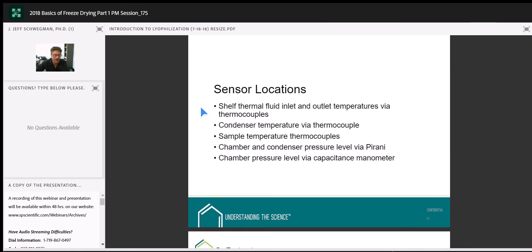First question: You mentioned the sublimation front is curved — is this applicable for both primary and secondary drying? What are the differences? There's no sublimation front in secondary drying. When primary drying is done, all the sublimation of ice is complete — we see the sublimation front come down as essentially a sphere at the end of primary drying. In secondary drying, all that's gone and we're just removing residual moisture, so there's no sublimation front associated with that.